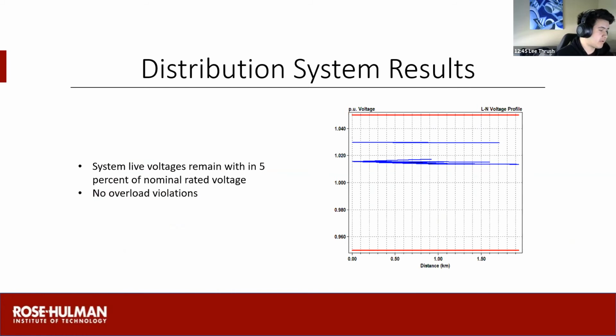This shows that our system remains within the voltage limitations. As seen in the figure, the red lines represent the maximum and minimum per unit voltages that the lines throughout campus can have, and the blue lines represent the actual voltage. As you can see, our voltages remain within those maximum minimums, and thus we don't have any voltage violations.